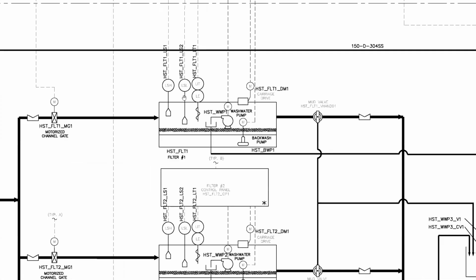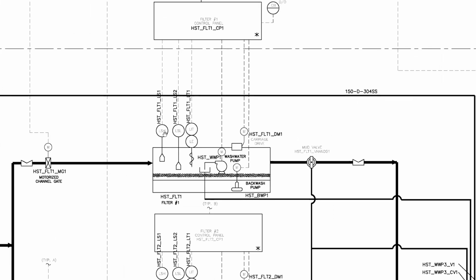So you can see here with the P&IDs, because you have an LSH, an LSL, an LIT, and an LE is a level element. So the level element goes into the level indicating transmitter. Here they're showing a tag for the device. So HST, for this client, it was Hagersville sewage treatment filter 1, and this is LT1. So that's filter 1 level. This is the filter 1 level switch low and the filter 1 level switch high. It's actually level switch high is LS1, level switch low is LS2.